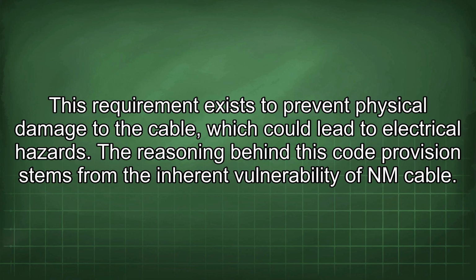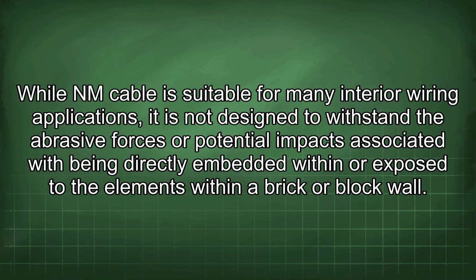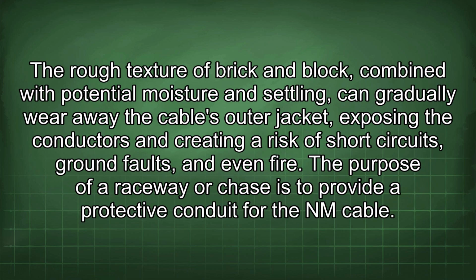The reasoning behind this code provision stems from the inherent vulnerability of NM cable. While NM cable is suitable for many interior wiring applications, it is not designed to withstand the abrasive forces or potential impacts associated with being directly embedded within or exposed to the elements within a brick or block wall. The rough texture of brick and block, combined with potential moisture and settling, can gradually wear away the cable's outer jacket, exposing the conductors and creating a risk of short circuits, ground faults, and even fire.